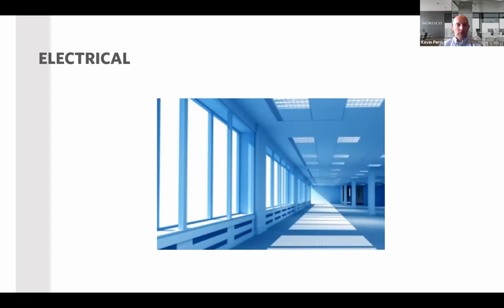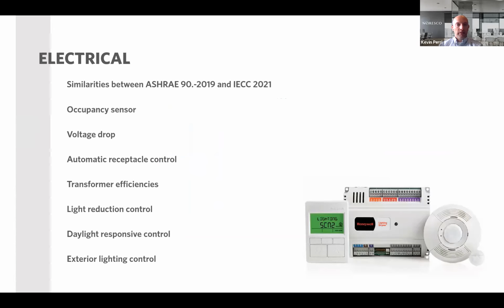So let's jump now to the electrical section. Now, I will point out that there are differences in how ASHRAE and IECC call electrical. I group them all into one. ASHRAE breaks them out into lighting versus power. So for the sake of this presentation, that's all grouped into the electrical category. Similarities: occupancy sensors. Occupancy sensors turn off after 20 minutes and turn on to 50% and also have manual control. Same both pathways. Voltage drop: the feeder conductors and branch circuits combined can't have more than a 5% voltage drop. Both pathways are the same.